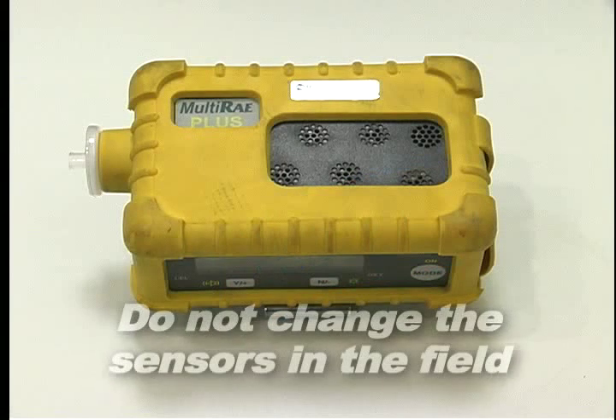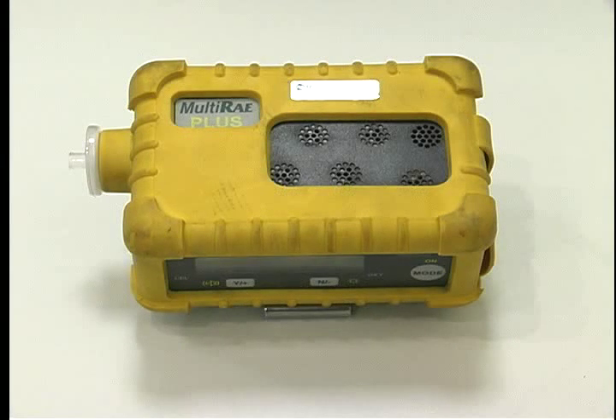Do not change the sensors in the field due to the need for calibration before use. The MultiRAE has three constants — O2, LEL, and PID — and can accommodate two additional sensors: ammonia, carbon monoxide, chlorine, hydrogen cyanide, hydrogen sulfide, nitric oxide, nitrogen dioxide, and sulfur dioxide. If PID was requested, the correct lamp will be in place.